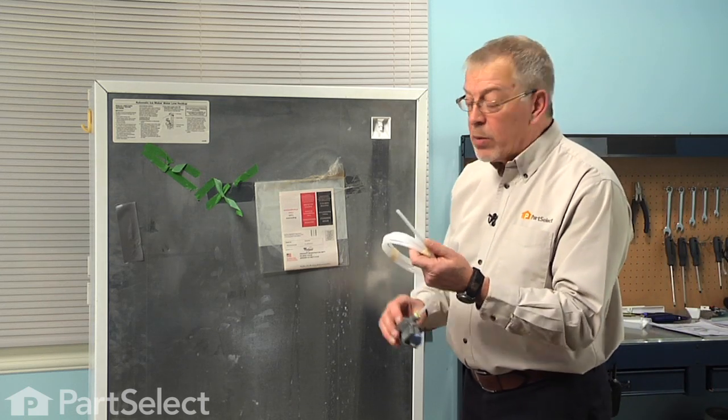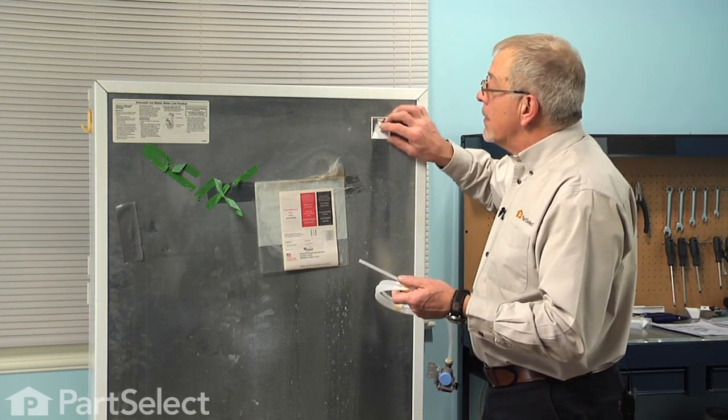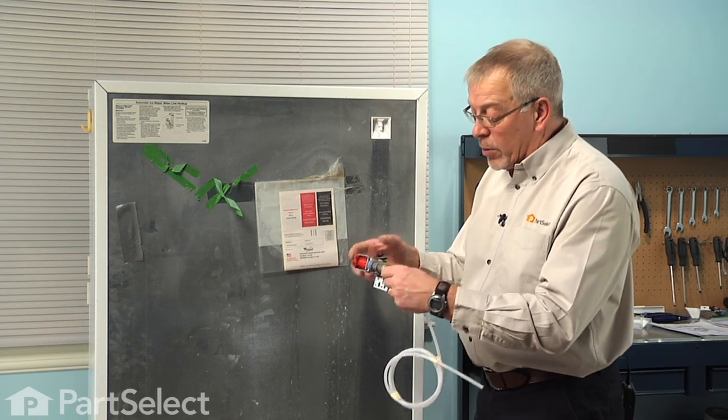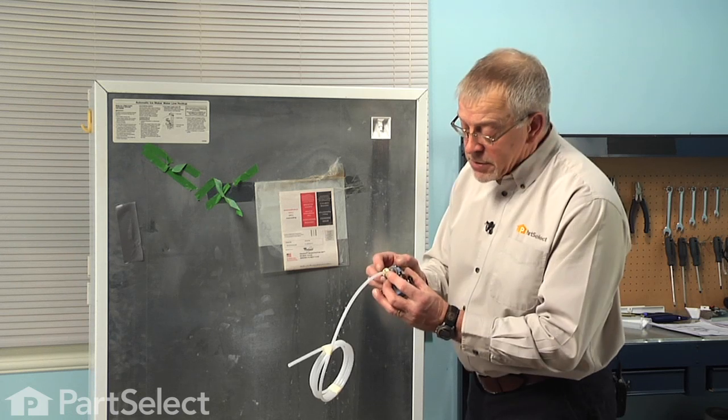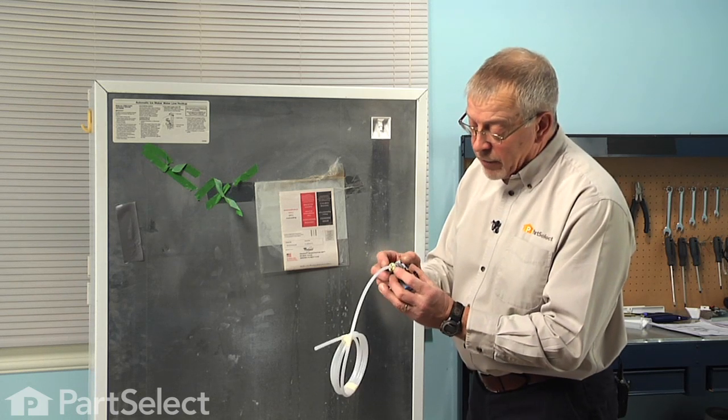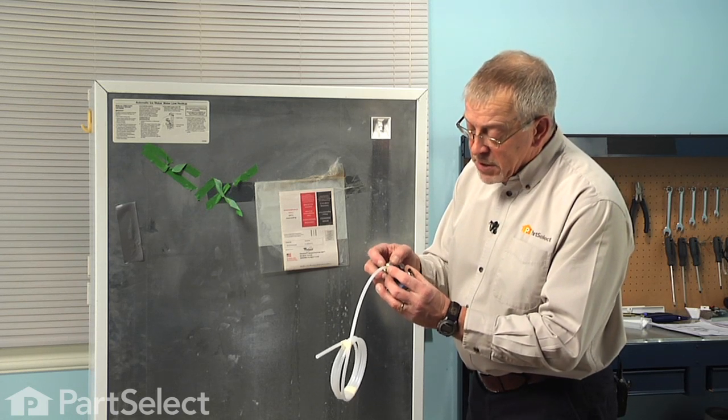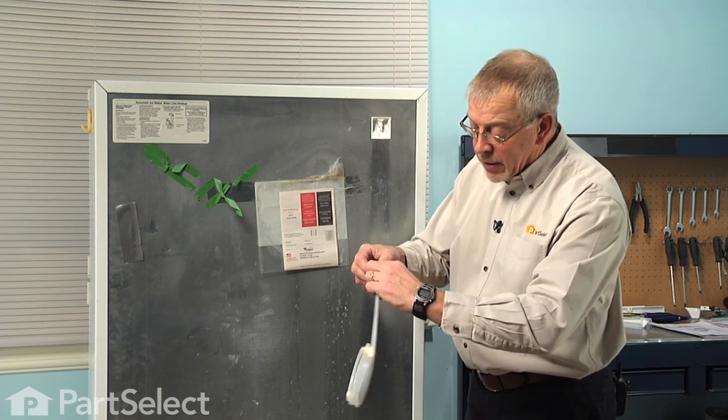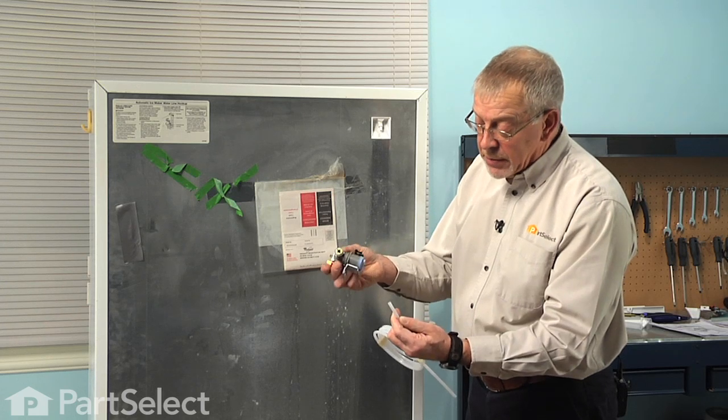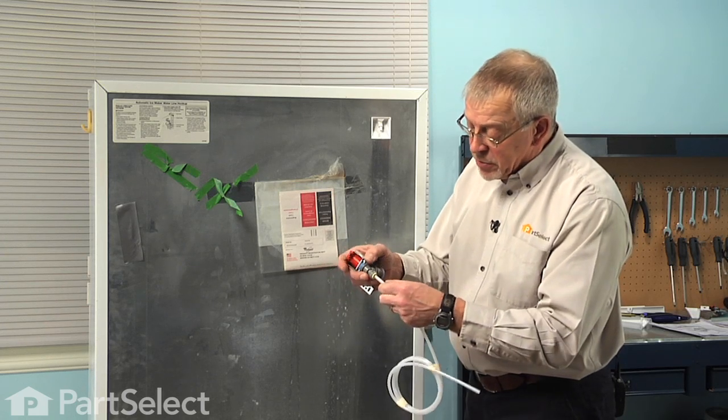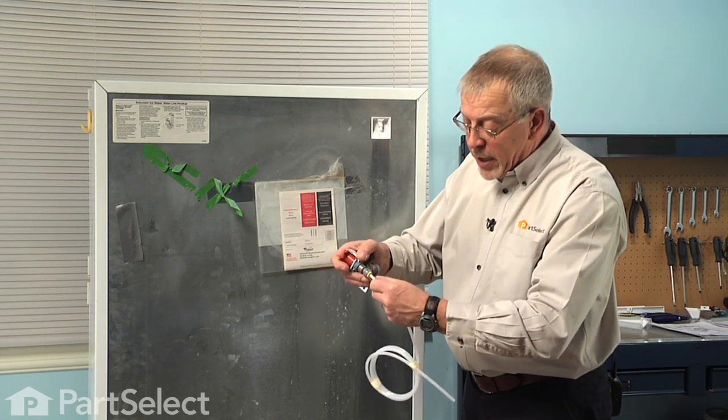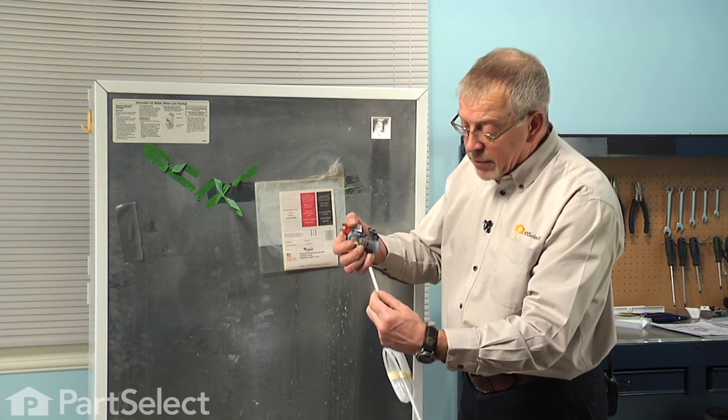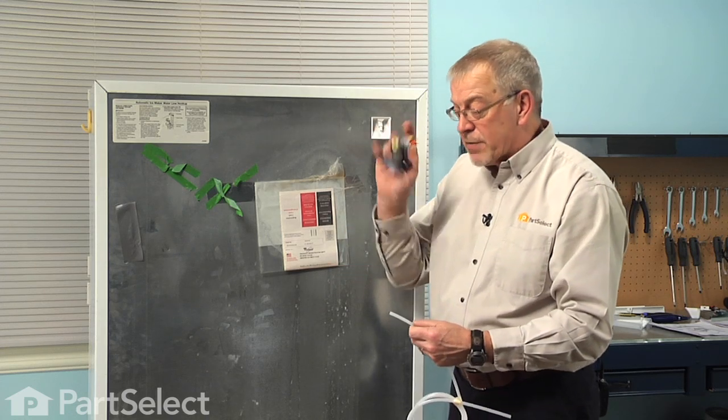Now next we're going to install the water line to the fill tube. Rather than have the valve hanging in the way here, we're going to disconnect it from the tubing. There's a little collet on the outlet of that valve. We simply depress that and push it directly into the valve and hold it there, and then the tubing will just pull out. When we go to reinsert it, we're simply going to push it all the way in, pull it back out and it will lock in place. So just depress that little collet and pull the tube out, and we'll set the valve aside for now.